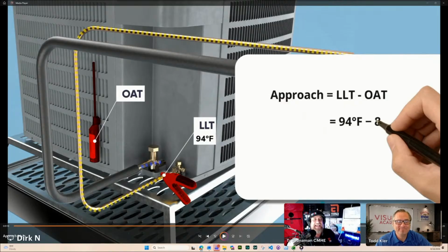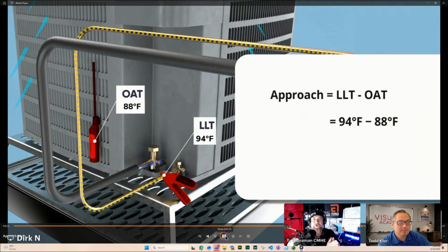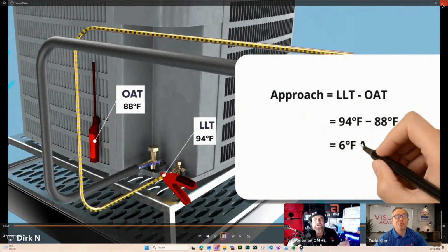So we see, hey, if our liquid line temperature is below the ambient, there's something else going wrong or out of calibration on your instruments, because it can just only get down as low as the outdoor temperature. So understanding what would be normal, it's the best case scenario. I can only get to this point. Hey, I'm beyond that. Something else is going wrong. Like, let's look at that. That's not normal. And so we'd go into looking at that.